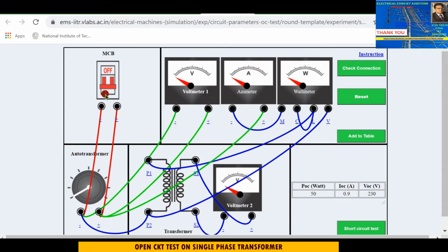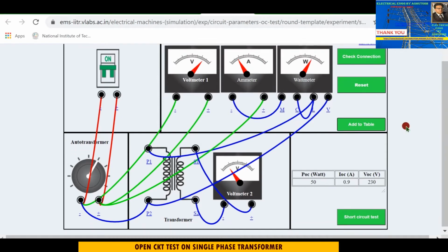Whenever you switch on the supply by clicking on it, it will turn green, as you can see. Then double click on the auto transformer and add to table. Whenever you add to table, the readings will be shown. This voltmeter is reading the supply voltage, the rated voltage of 230 volt. This ammeter is connected in series with the primary and is reading 0.9 ampere, which is also called the no load current. And this is the iron loss or core loss, 50 watt. This wattmeter W1 is connected at the primary side, and it is giving a 50 watt reading.